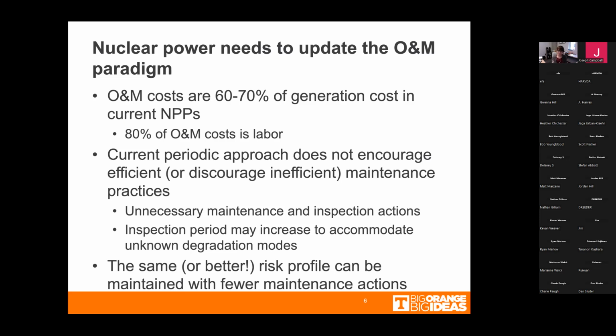So you have corrected sensors that were out of calibration, but you've introduced calibration errors into sensors that were just fine before. And so when we do this unnecessary inspection, there's a chance that we're going to introduce a fault or a problem into the equipment that wasn't there to begin with. And so we actually see that the time-based periodic activities approach to inspection and maintenance could actually increase the risk profile of operating nuclear, just because we might be inserting some faults through imperfect maintenance activities.